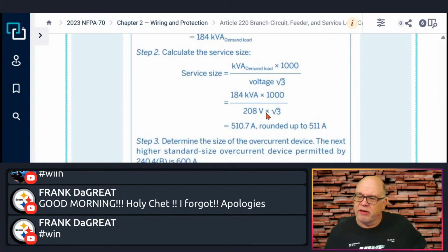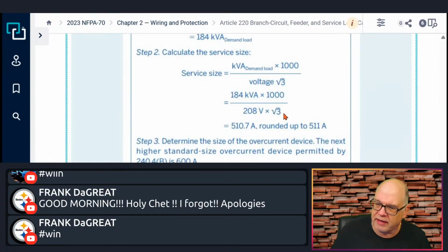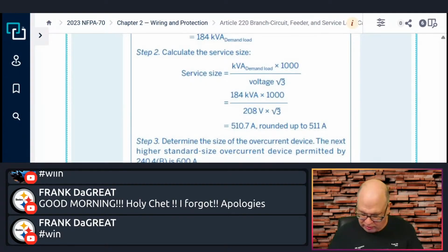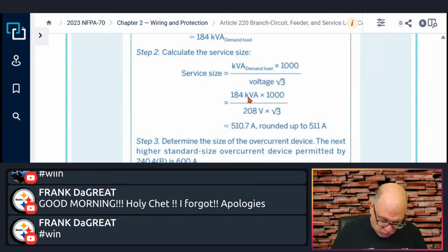And then, of course, down here, it is 208, and we have the square root of 3. So it's 208 times 1.732, and that is 360.256 if you want to carry it all the way out. So basically, we're doing 184,000 divided by 360.256, and that is 510.7, and that's going to be rounded to 511. Whoop, whoop. All right. So that's what we'll be doing.